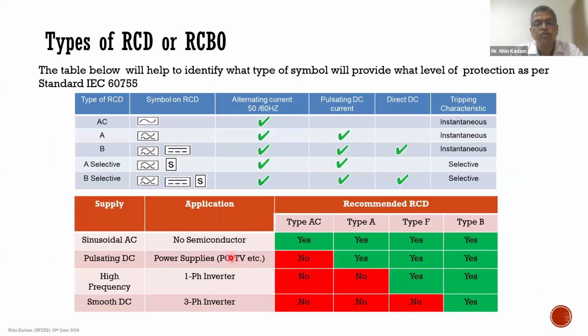So this is also a summary where it is specified here. So type B, if you see, this green specifies where it can be used, the green cells. So type B has to be used where you have a smooth DC coming out, and there are chances of smooth DC leakage currents on the site and can create a shock.